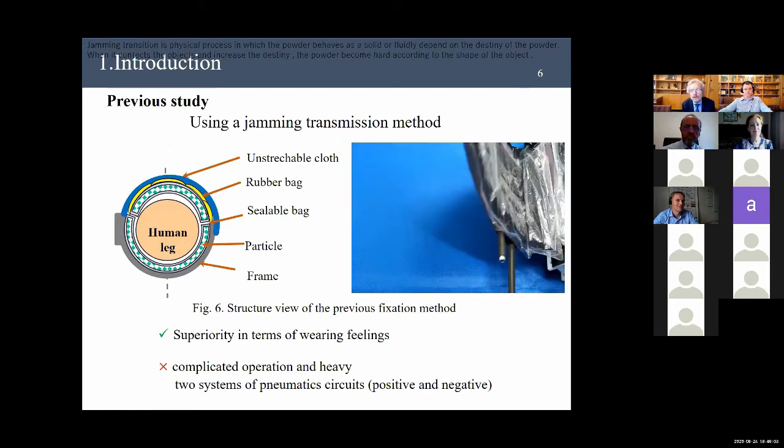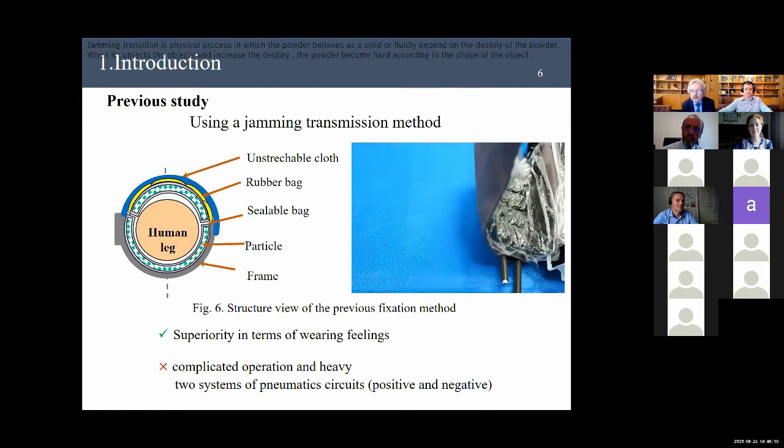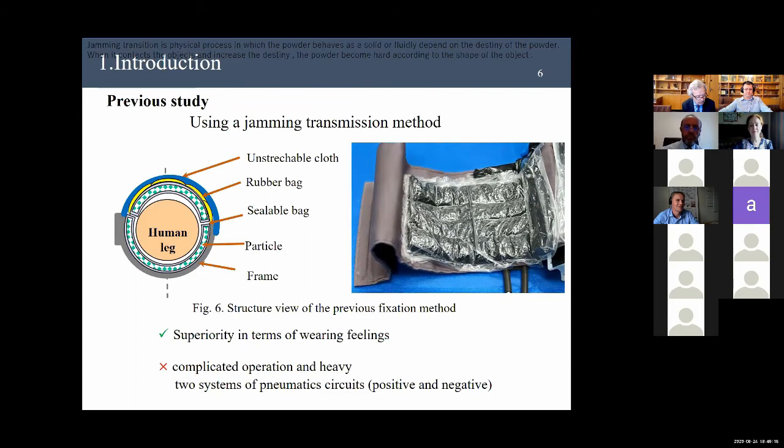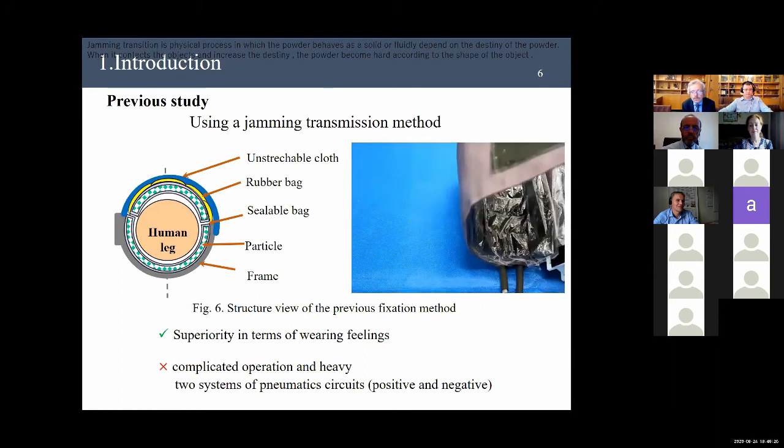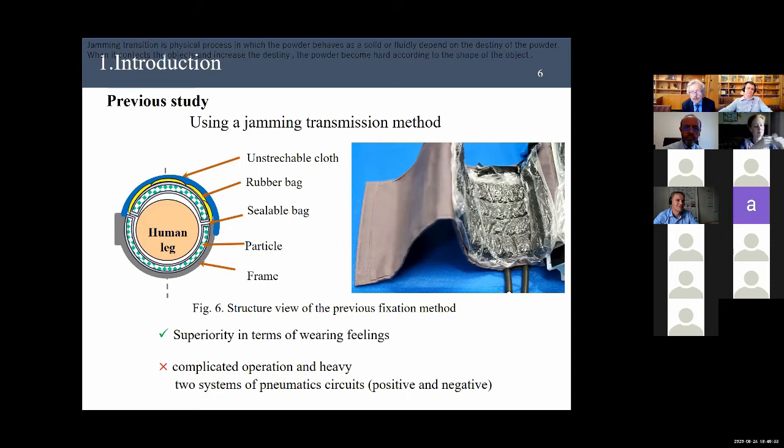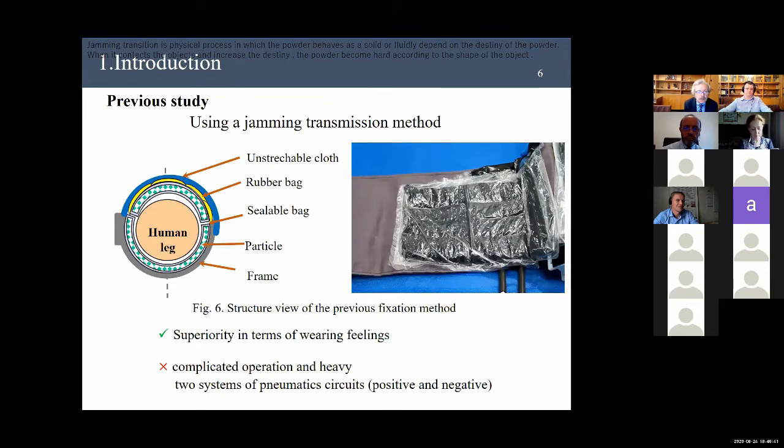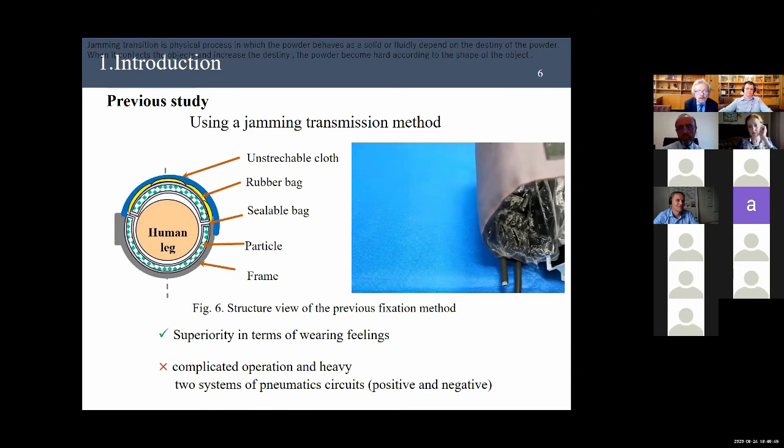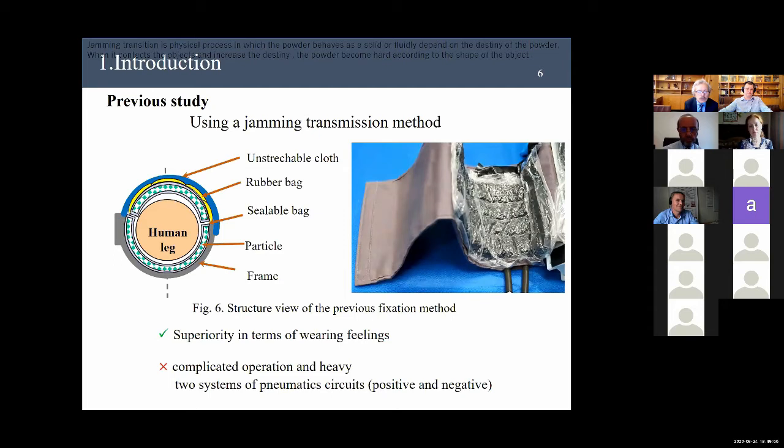In a previous study, we proposed a fixation method using a jamming transition that can deform based on body shape. Jamming transition is a physical process in which the powder behaves as a solid or fluid depending on the density of the powder. When it contacts the object and increases the density, the powder became hard according to the shape of the object. Additionally, we conducted a sensory evaluation experiment and compared the existing fixed part with the prototype fixed part. This experiment confirmed that the fit was better when compared to that of the existing fixed part. However, the fixed part using jamming transition required two pneumatic systems, namely positive air pressure and negative pressure generation.